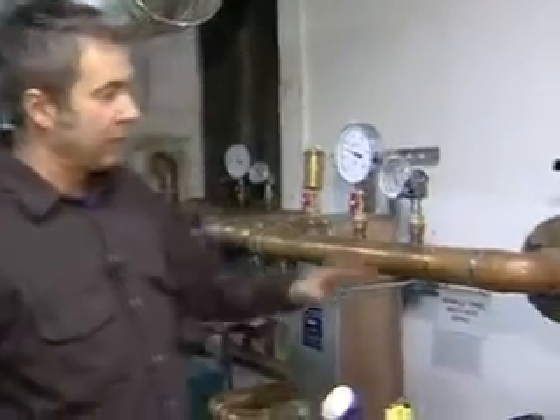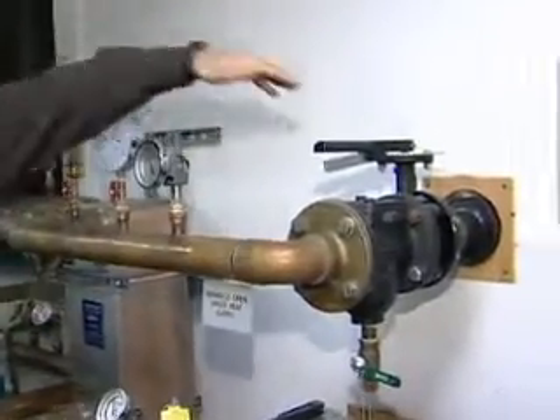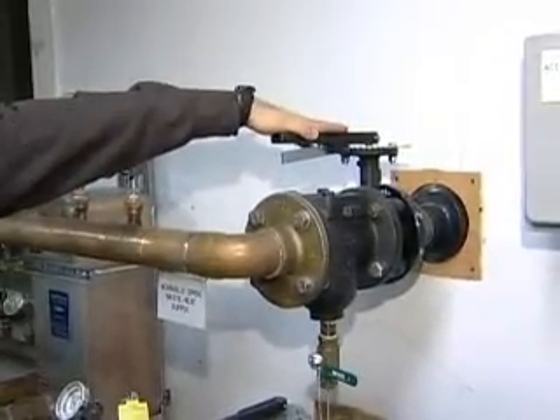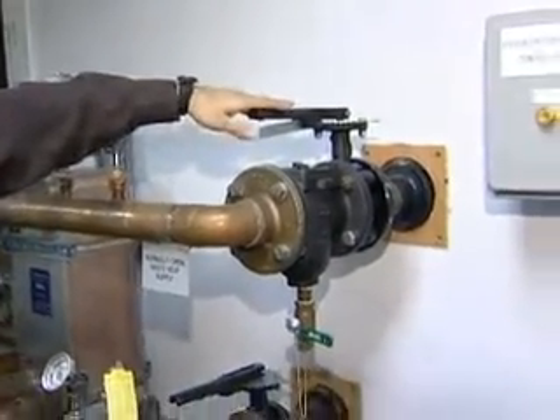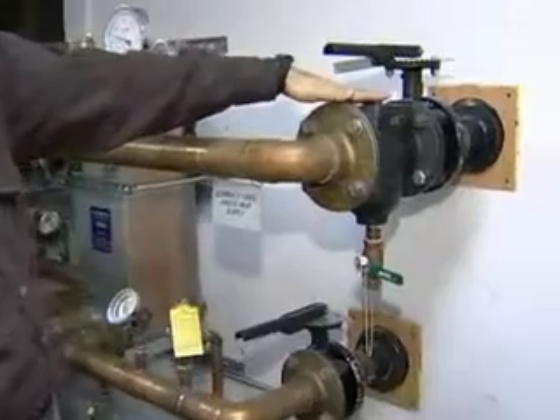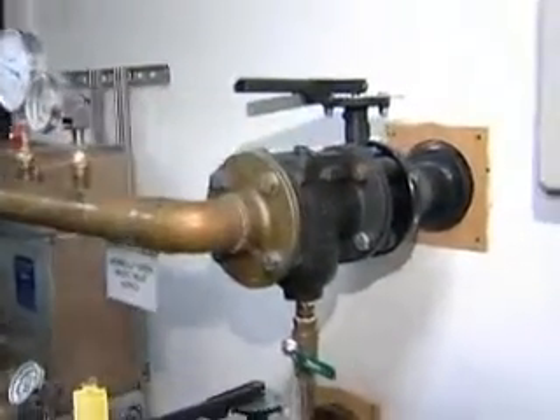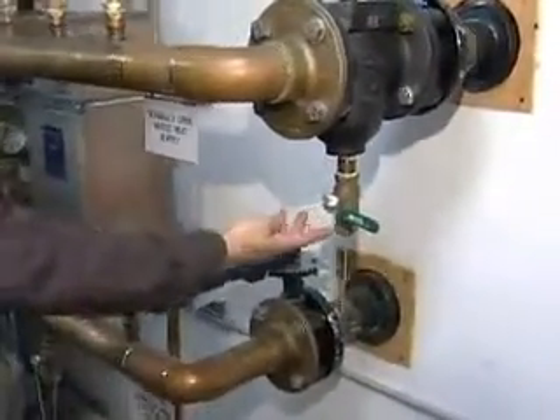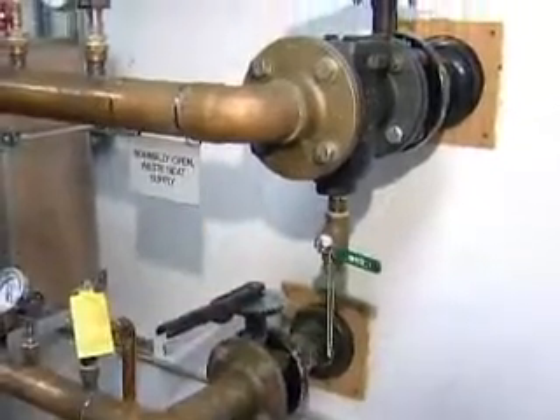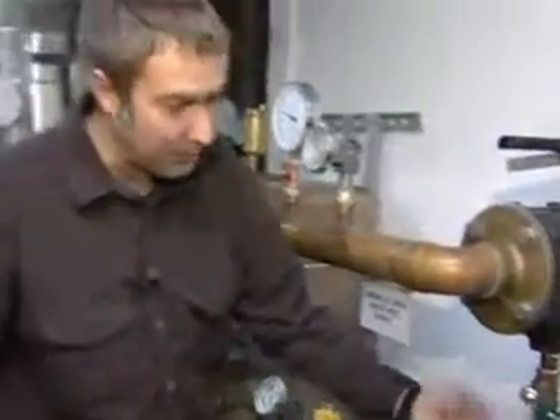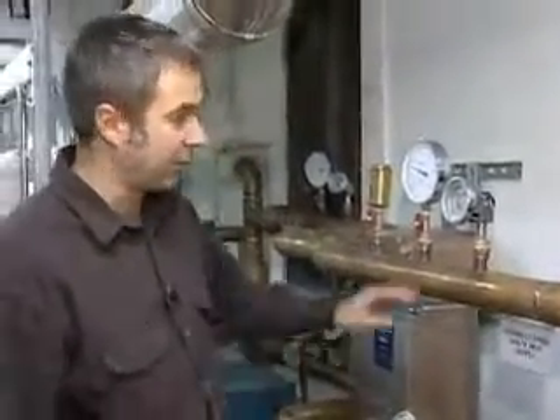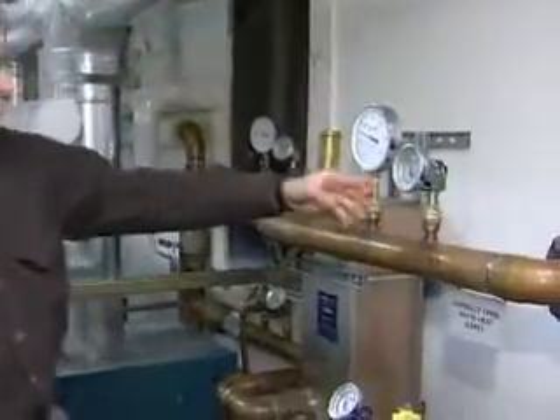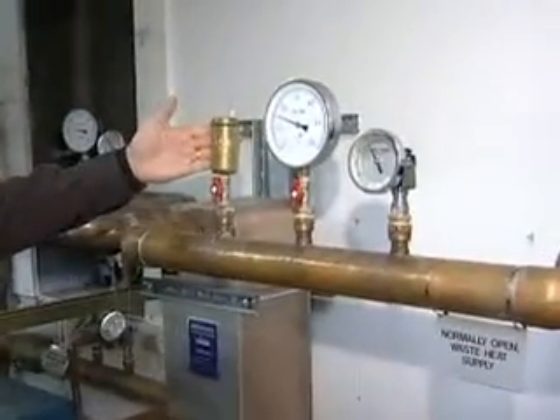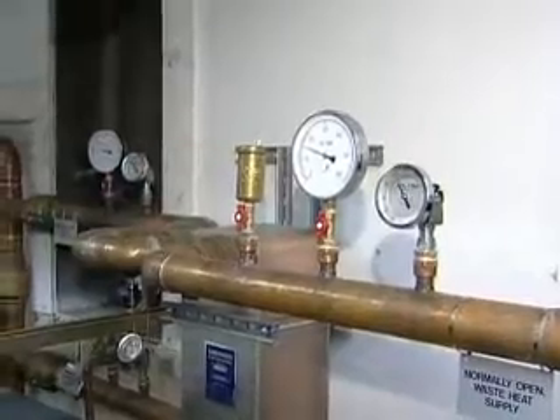Now we're over at the water treatment plant where the waste heat from the power plant is delivered to. So here's where the piping enters the building. We have a valve, normally open valve, for the heating supply coming in. We have a strainer here, just like we had over in the radiator room, and we can see a good clear shot of it. The strainer has a drain valve on the bottom where if it ever gets clogged, we can open that up, blow down, and clear the debris out of it. We have a thermometer, pressure gauge, automatic air vent, which needs to be bled periodically.